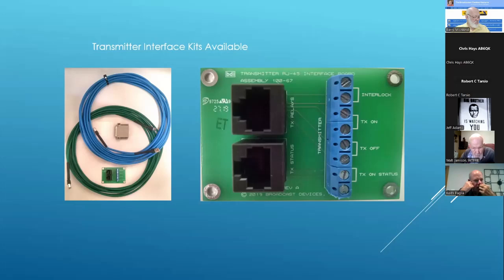It's two Cat5 cables, really just Ethernet cables. It's not Ethernet, obviously, but just two cables that you can connect to these interfaces that go inside the transmitter. Then you get the basic connections, the external interlock input for the transmitter on and off connections. And if the transmitter has an on status and you want to see that on the controller, you can bring that cable back out, and that goes into another connector on the controller.